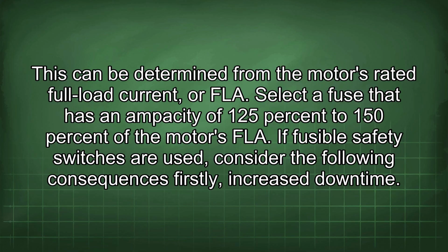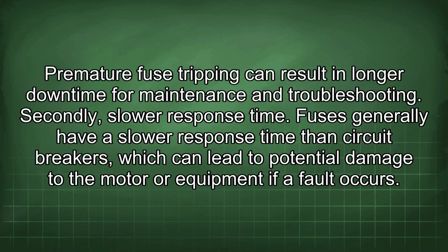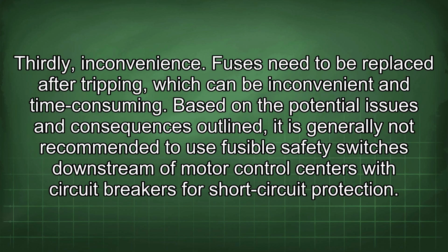Firstly, increased downtime. Premature fuse tripping can result in longer downtime for maintenance and troubleshooting. Secondly, slower response time. Fuses generally have a slower response time than circuit breakers, which can lead to potential damage to the motor or equipment if a fault occurs. Thirdly, inconvenience. Fuses need to be replaced after tripping, which can be inconvenient and time-consuming.